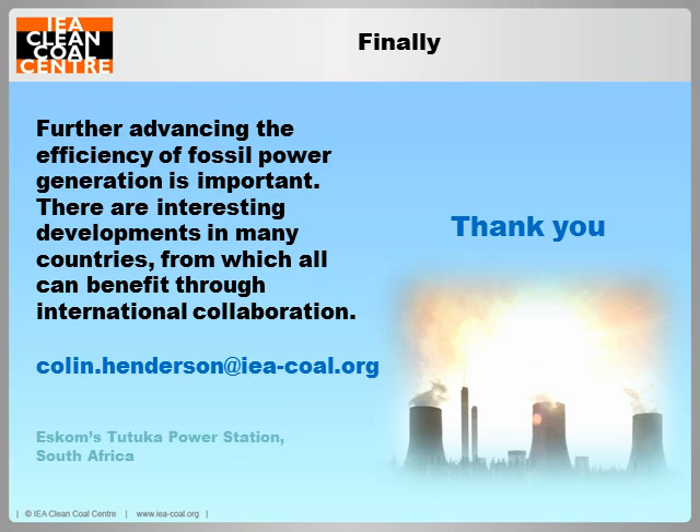Another question: retrofitting conventional old plants to supercritical and ultra-supercritical — is this being considered? I didn't mention it, but it is in the report. It's something which has been considered in countries including the UK, where feed studies were done for conversion of subcritical to ultra-supercritical. But really all you're keeping is the very large common services like the cooling system, the FGD, the coal supply and so on — almost everything else has to be replaced: a new boiler, virtually all the turbine, new steam piping and so on. And the upshot is that there have actually been virtually no projects emerging from these studies, but they have certainly been considered.